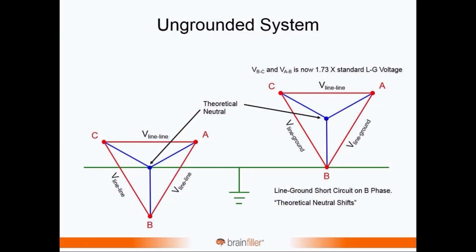Yes and no. It depends on how the system was designed. A true ungrounded delta, if it's properly designed, is designed for continuous operation. But when you have a fault on, let's say, the B phase, yes, it goes to 0, but you still have full phase-to-phase voltage among all the phases. So you still have the complete phase-to-phase voltage from A to C.